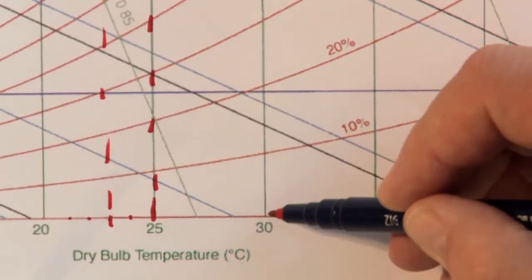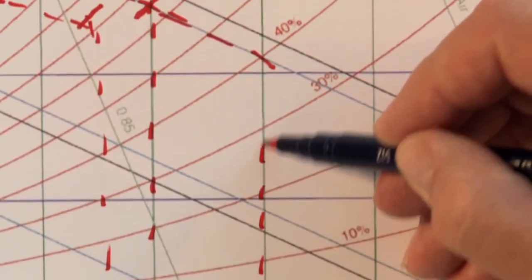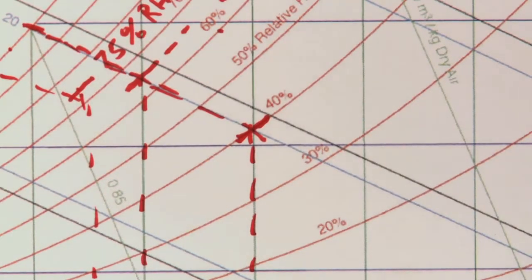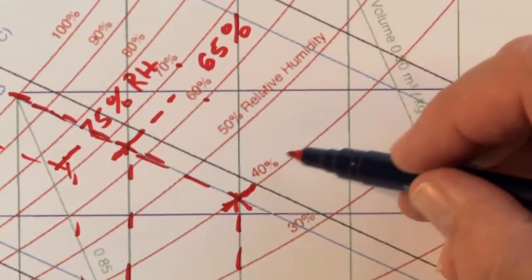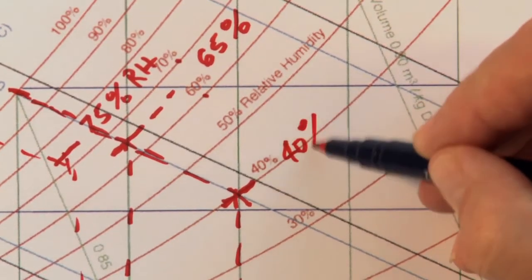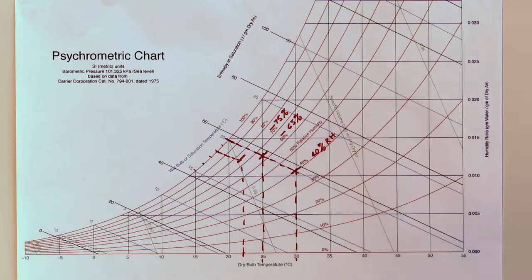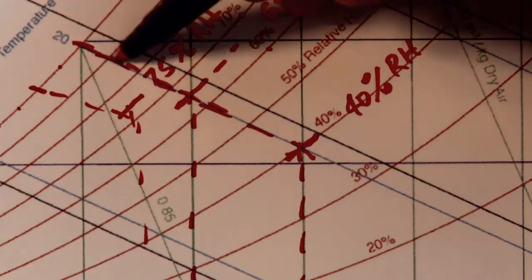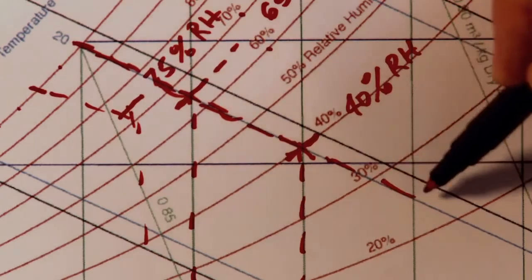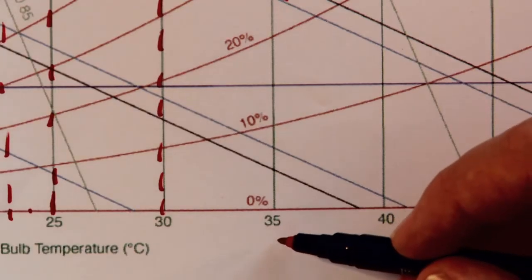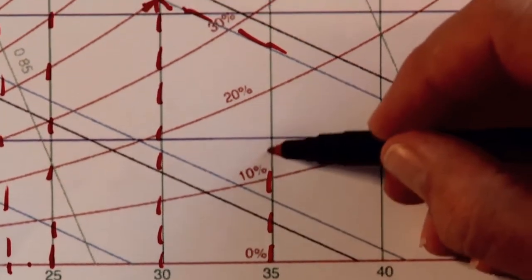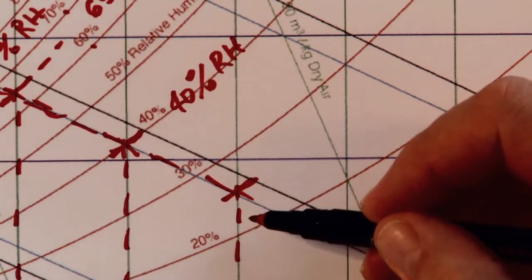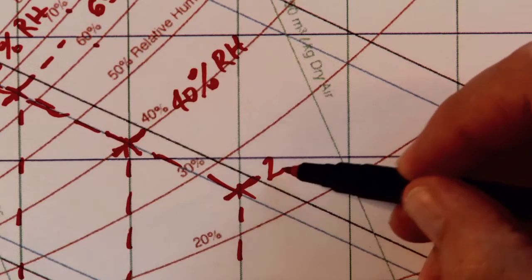Here we have 30 degrees Celsius plotted on this curve, and the intersection of these two points tells us the relative humidity — in this case a reading of 40%. One more example: with a wet bulb of 20 degrees Celsius and a dry bulb of 35 degrees Celsius, the intersection of these two points gives us a relative humidity of 25%.